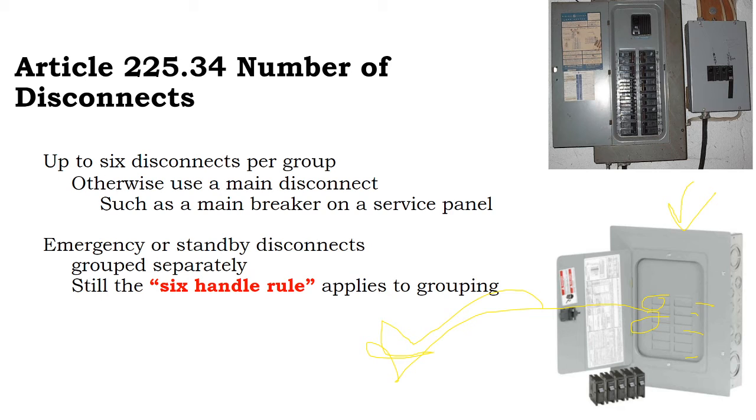Maybe the home of the future is a 200 amp service because we have all this on-site power that says we don't need more than that coming in from the utility. But then the 200 amp service panel is really just there to break out into smaller, 100 amp service panels for a variety of smaller on-site battery systems and isolating automatic transfer switches and stuff like that. All this stuff gets really expensive when you get into above 200 amps and really above 400 amps for that matter.